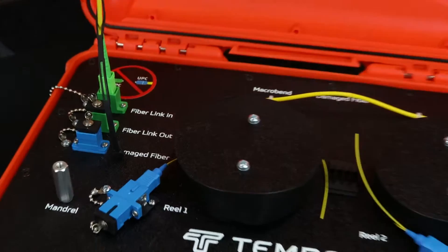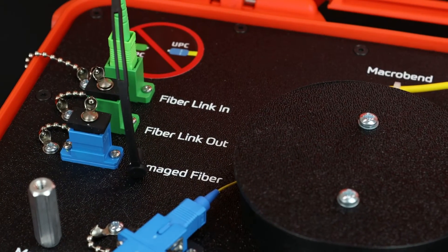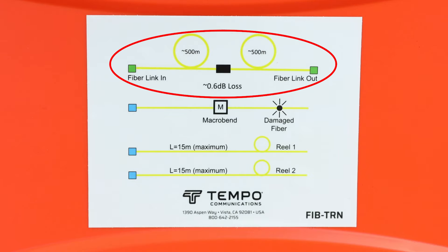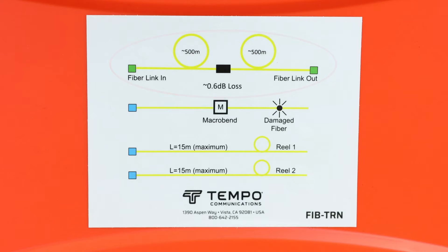The fiber link in port provides access to a 1000 meter fiber that is terminated at fiber link out. At the approximate 500 meter mark, there is a faulty connector with an approximate loss of 0.6 dB and a reflectivity of minus 45 dB.